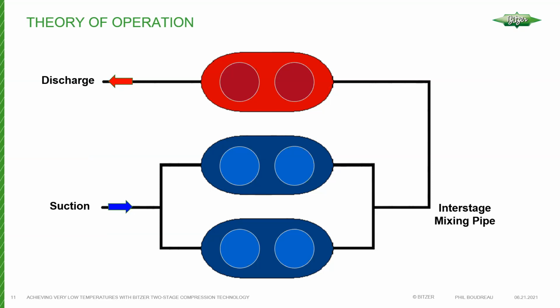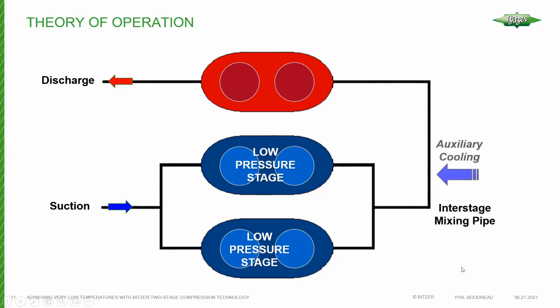So we can see our suction line is split via the suction manifold, or header, into the 2 groups of cylinders, 2 groups of 2. So we have our low pressure stage, and then on the discharge, they're paralleled, so they're coupled together, and then they travel through this interstage mixing pipe. But the next thing they have to do, we have to cool the motor at some point, but we need to also inject some form of auxiliary cooling. So this will be in the form of a refrigerant from the cycle that we're going to inject into the circuit. So here's our motor heat.